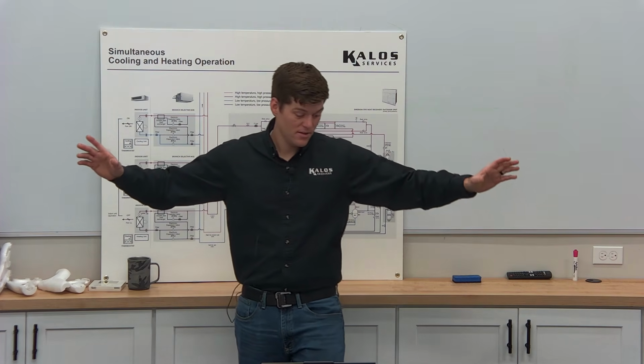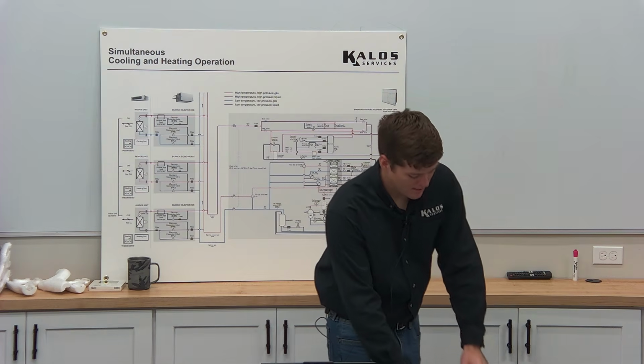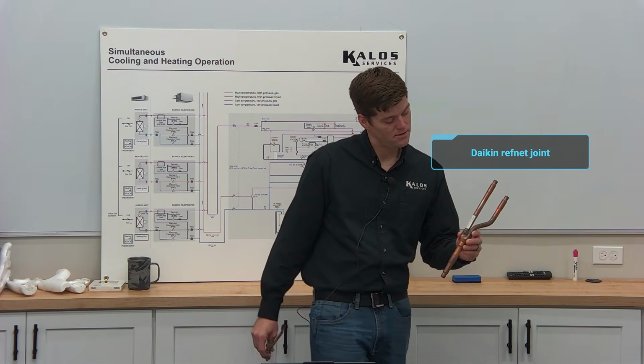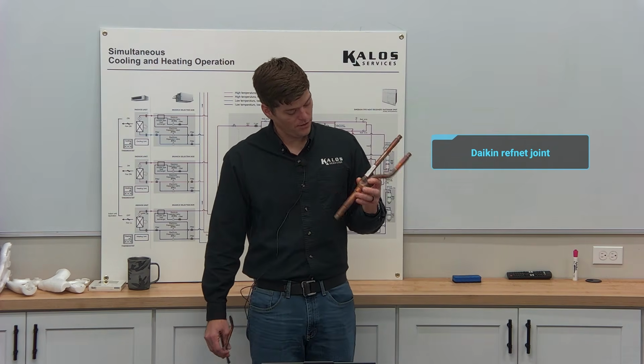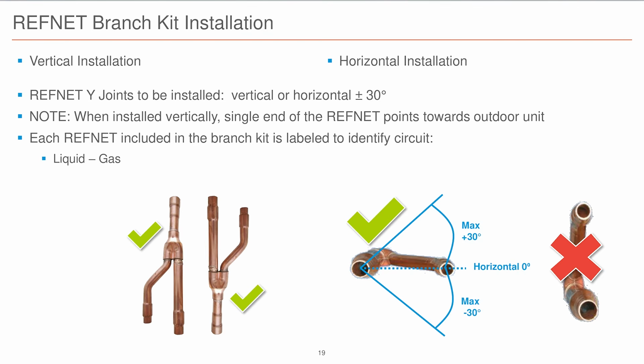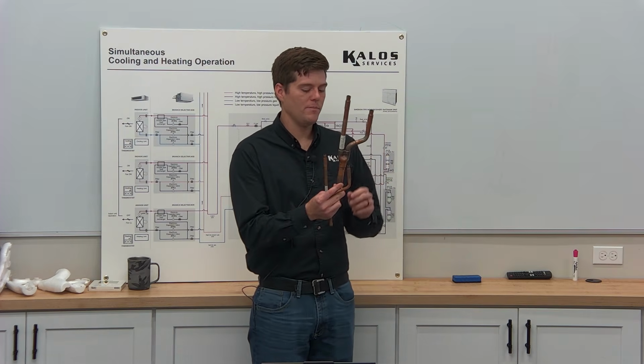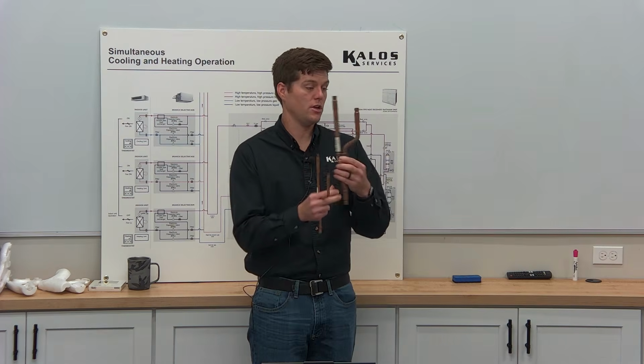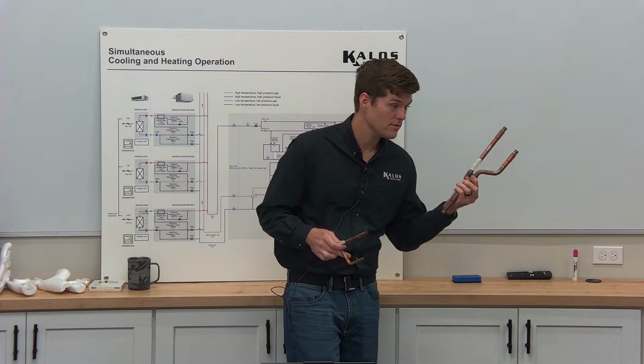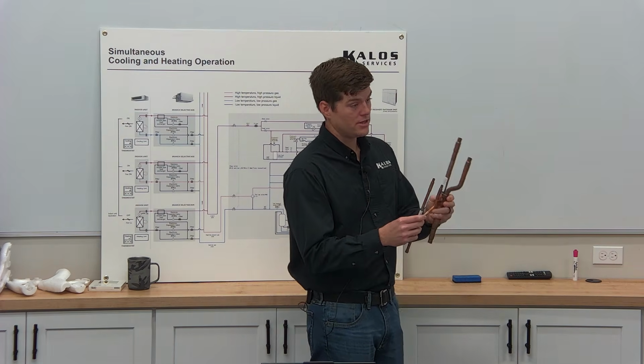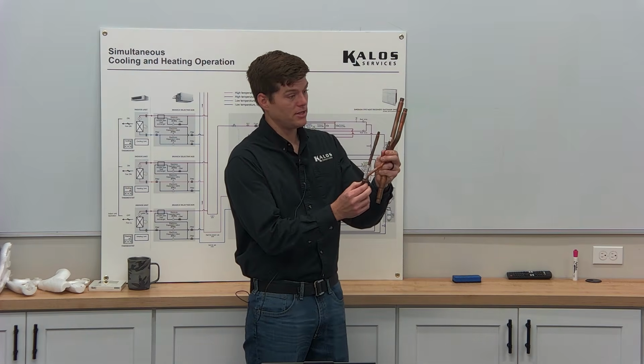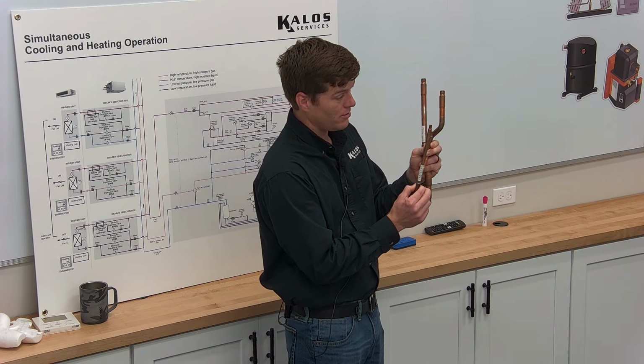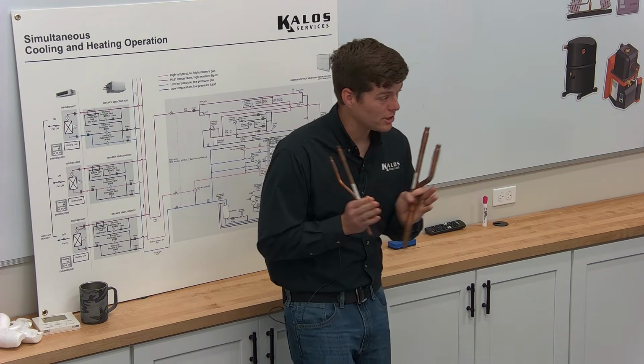What are these actually called? This is made by Daikin. This is called a Refnet. The reason is that they did a bunch of scientific testing. Obviously, they invented the technology, and they've changed it only a very short time ago to a different type. The way it's set up, this is going to be a suction, or hot gas, and this is your liquid.